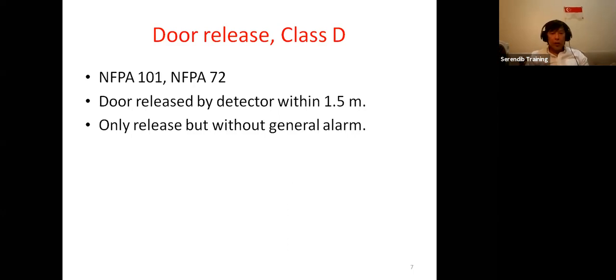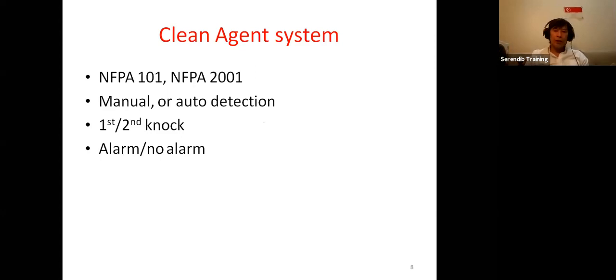And also, this does not raise a general alarm in the building. It only releases the door leaves and puts them into their normally closed position. Now the next one is the clean agent system.